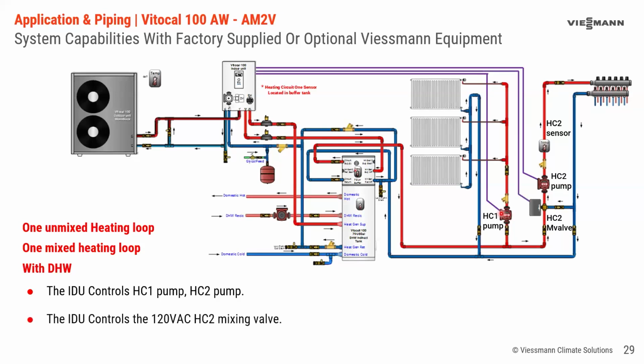And the indoor unit will also control 120 volt output, powered open, powered closed, to the mixing valve. Now, this is by factory designed for the Viessmann 120 volt mixing valve. So the timing is correct for our valve. If you're going to use somebody else's mixing valve, then you would have to go into the control setup and set the stroke time for your valve to match the timing in the indoor unit control logic. Again, the simplest way to do that, use a Viessmann valve, and there's no adjustment you have to make to the timing because we've designed this for the Viessmann valve out of the box.